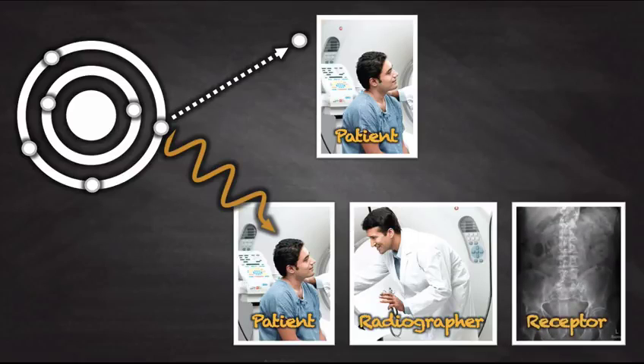And then finally, the scattered photon might be scattered out of the patient and towards the receptor. Compton scattering photons decrease image quality by decreasing image contrast. The use of radiographic grids helps to prevent scattered photons from reaching the receptor.